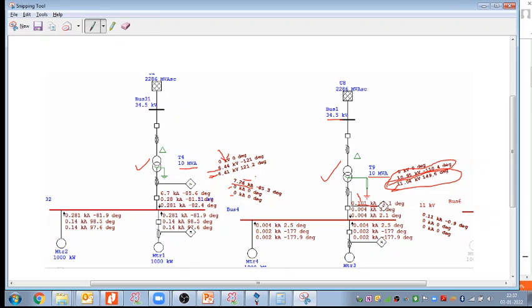If the core insulation is damaged, you cannot fix it at the site or in your rewinding shop. You have to send this motor or generator back to the manufacturing company. They will again make the core insulation, the winding, the rewinding, and it will take more time, maybe 2 or 3 months. And if you are taking this machine from China, it is going to take even more time, and your process industry is stopped.